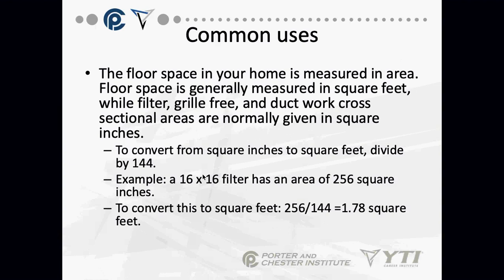A 16 by 16 filter has an area of 256 square inches. Divided by 144, that equals 1.78 square feet. These conversions are important when talking about airflow and ductwork size. Floor space is measured in square feet, while ductwork uses square inches — knowing how to go back and forth is essential in the field.